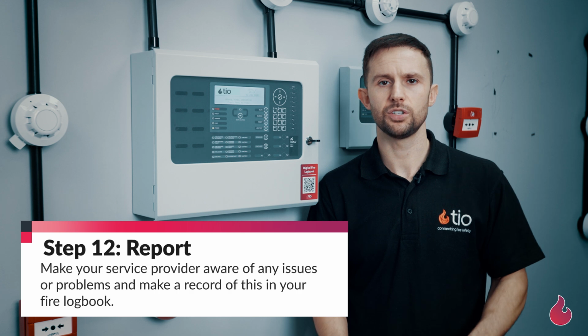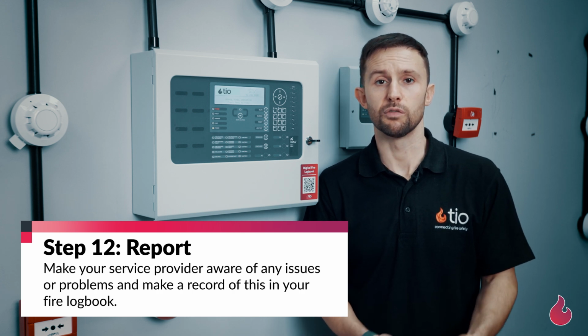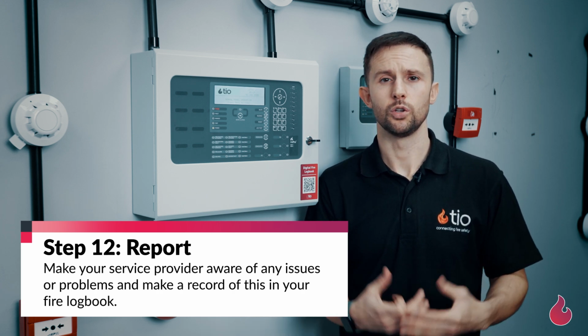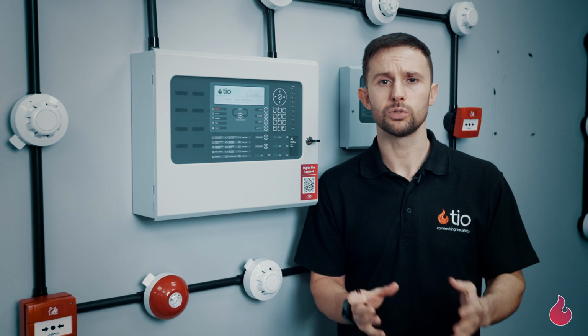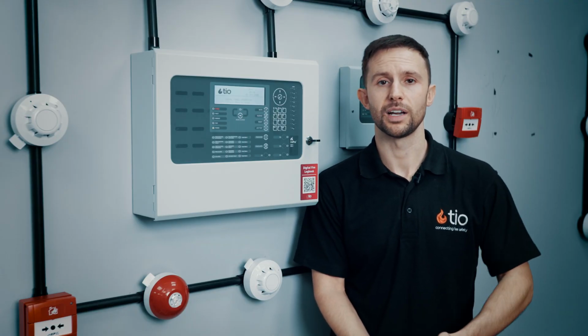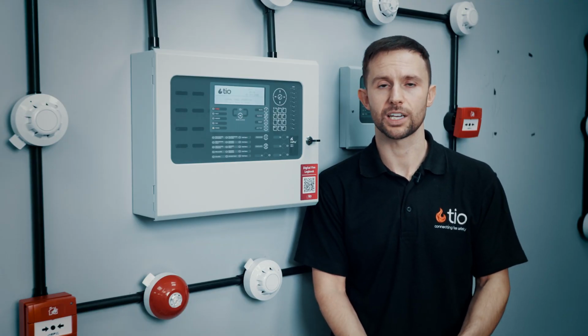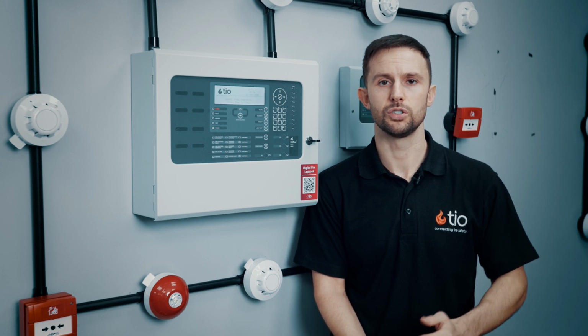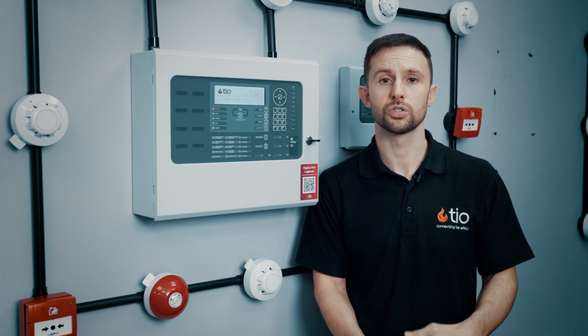If you spot any issues while doing a weekly fire test, for example, the sounders didn't activate, your key got stuck, or the fire alarm panel didn't go back to a green condition, make a record of this in your fire logbook and immediately contact your fire alarm maintenance provider. It's really important to make sure the information about a weekly fire test in your logbook is accurate, as this can be used as due diligence defence if there was a fire in your building.